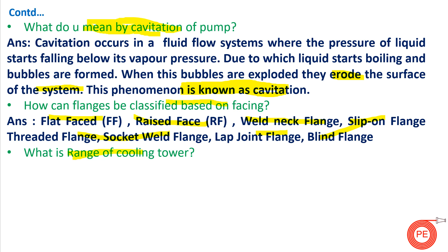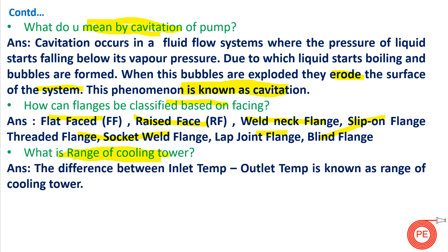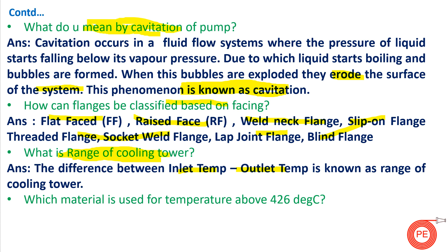What is the range of a cooling tower? In a cooling tower there are two important terms: range and approach. Range is the inlet temperature minus the outlet temperature. For example, if inlet is 45°C and outlet is 40°C, the range is 5°C. Approach is the outlet temperature minus the wet bulb temperature. This is the basic difference between range and approach of a cooling tower.